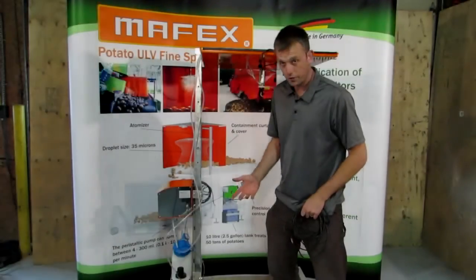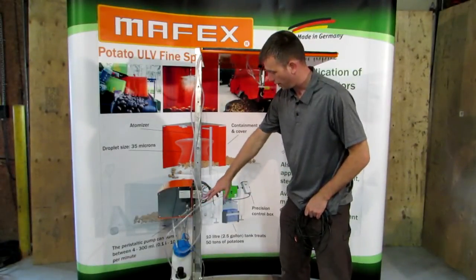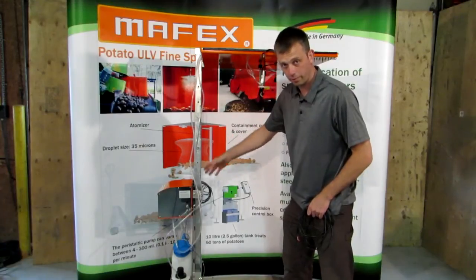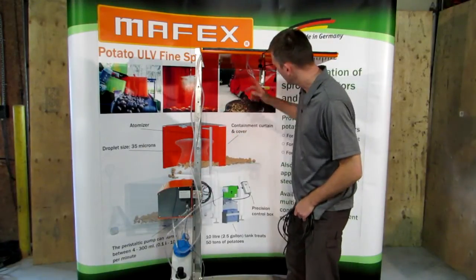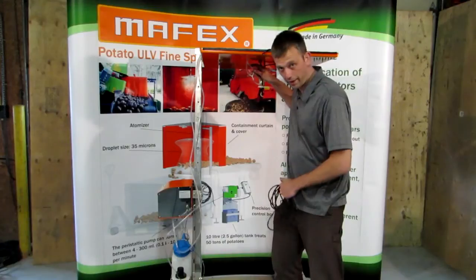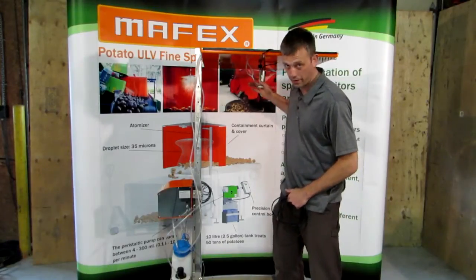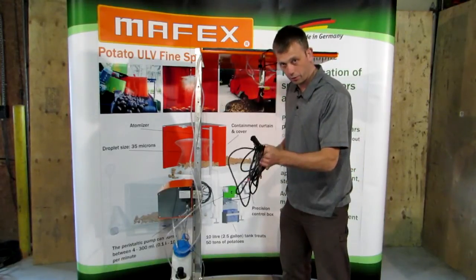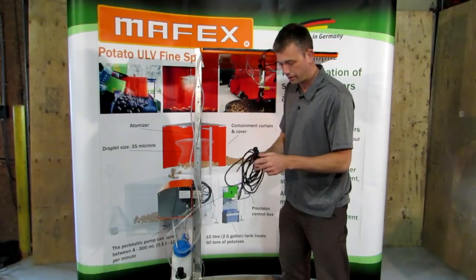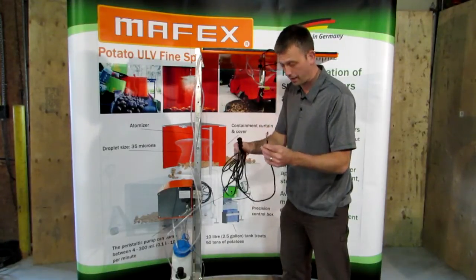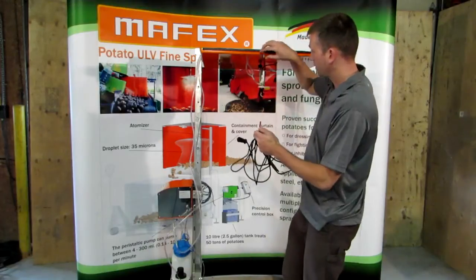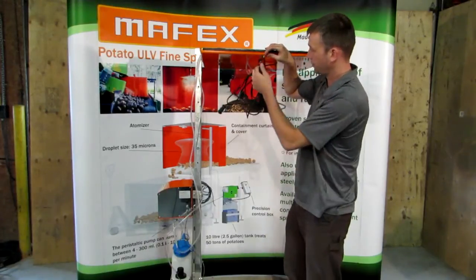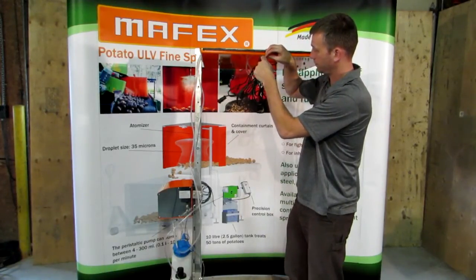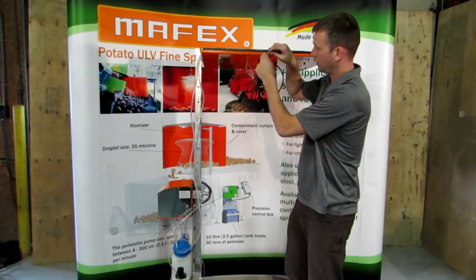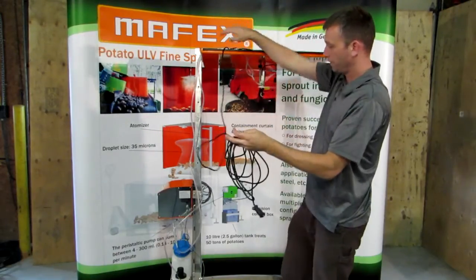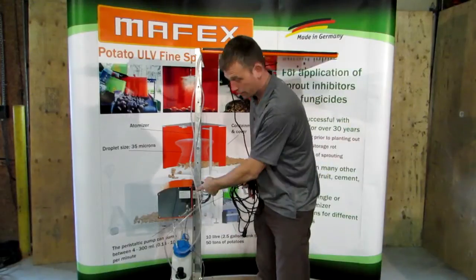Okay, so now we have the hoses installed and shortened. The two hoses coming up, one from the pump, one from the flush tank, and then they're joining together on a Y and going into the atomizer. Next we'll run the cable to the atomizer. You'll have got this cable in your package. It connects to the atomizer's connectors here. And then we're going to run it down into the pump box.